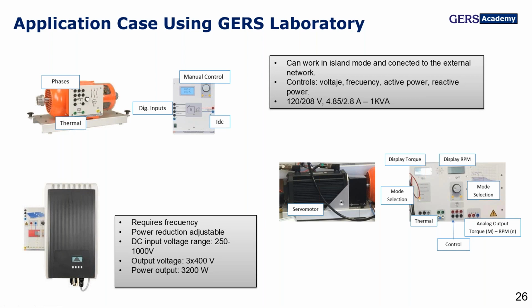Basically, if we would like to increase or reduce the voltage, we will have a variation of the excitation of the system, where we will be increasing or reducing the reactive power.